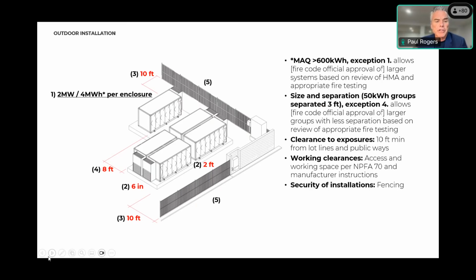Number four is really just between front to front, and that's usually dictated by the work that needs to go in, because they need to do maintenance. They need to make sure that they can open up the doors completely and do the maintenance that's required. So that 8 feet is actually in the National Electric Code.